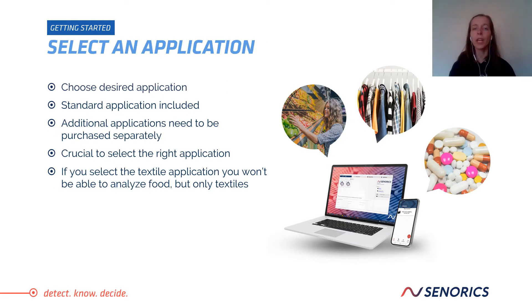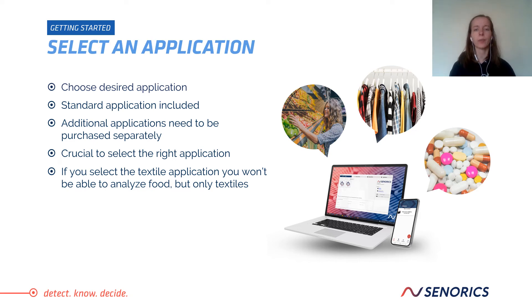Following the successful calibration, you will need to choose your desired application. There is one standard application already included when you purchase the SenoCoder. The textile application enables you to identify silk, wool, cotton, and polyester. Any additional applications need to be purchased separately. It is crucial that you select the right application, as this is the only way to ensure that the SenoCoder can successfully identify and quantify the analyzed materials. For example, if you select a textile application, you won't be able to analyze food — you will only be able to analyze textiles.